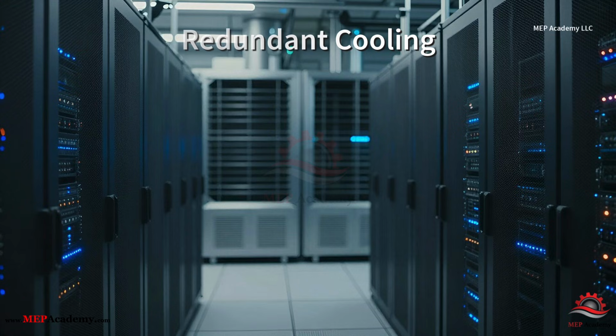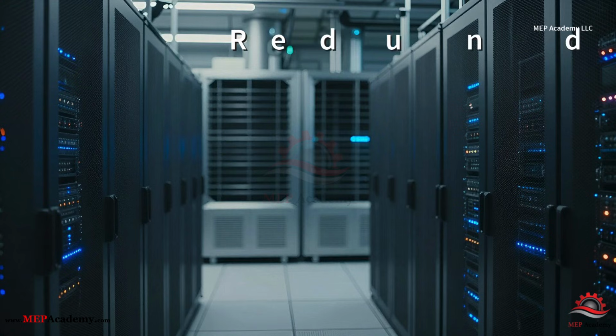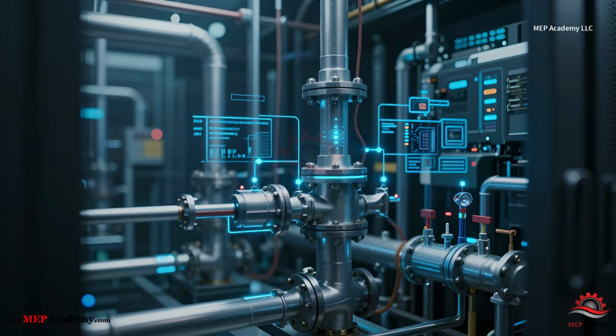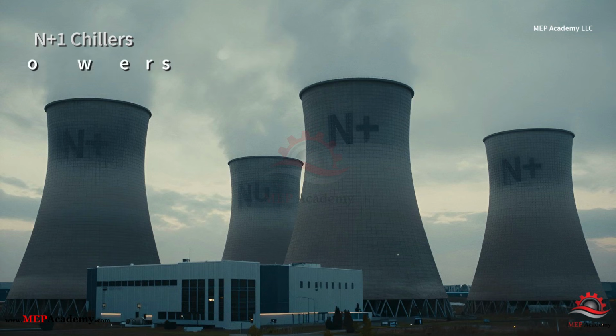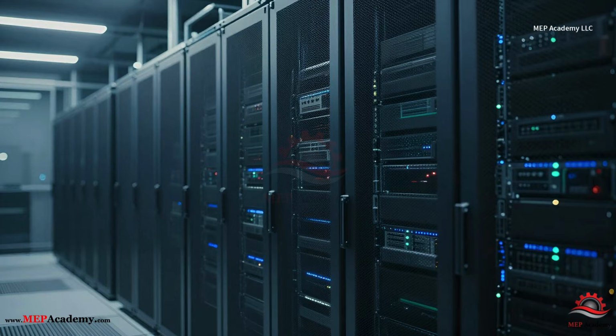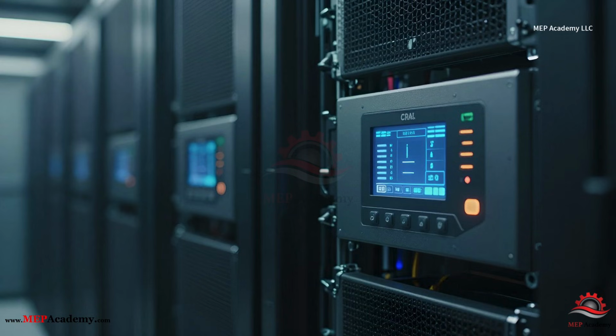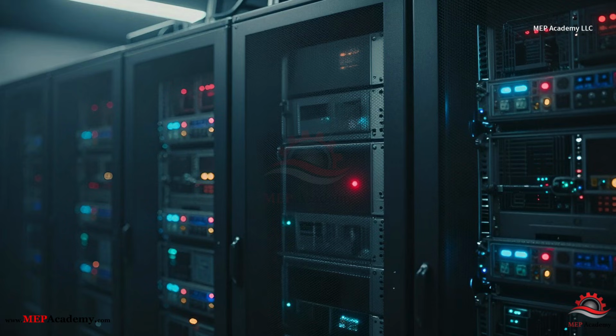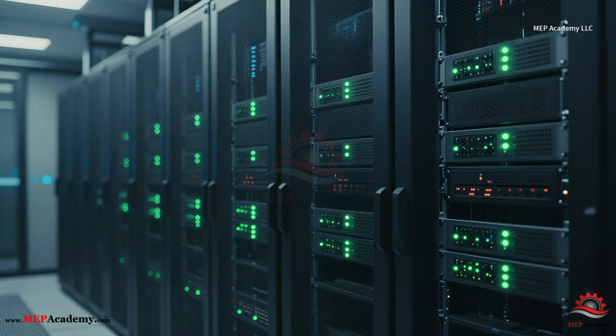Cooling systems in large data centers often combine multiple layers of redundancy. For example, a chilled water system may include N+1 chillers, N+1 cooling towers, N+1 condenser water pumps, and N+1 chilled water pumps. Inside the data hall, cooling units such as in-row coolers or CRAH units may also follow an N+1 configuration. If one cooling unit fails, the remaining units increase airflow and maintain temperature control. This layered approach ensures that the failure of a single component does not cause the servers to overheat.